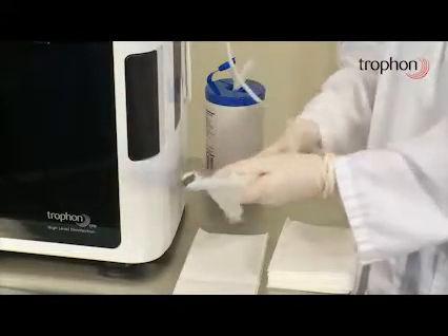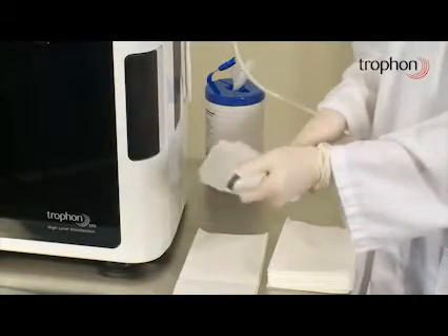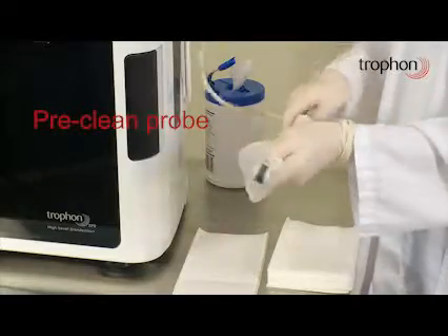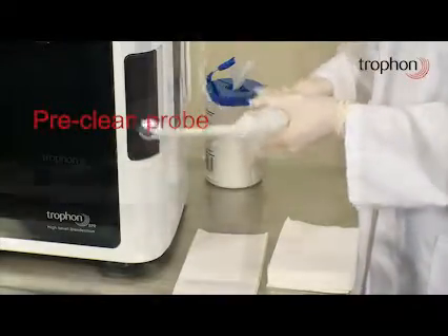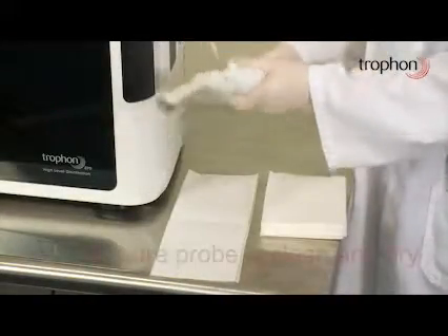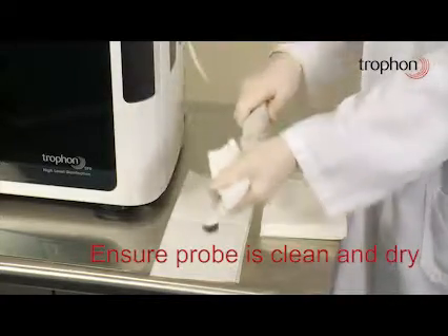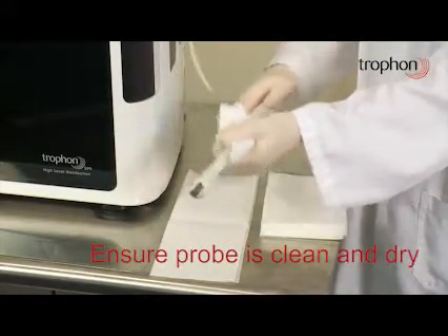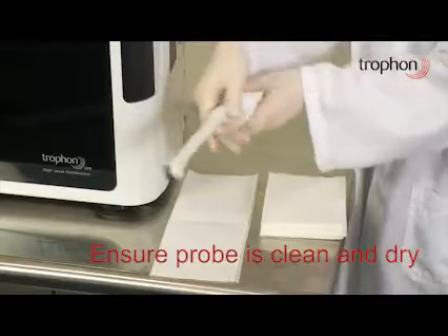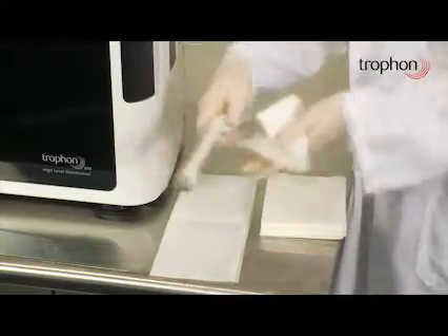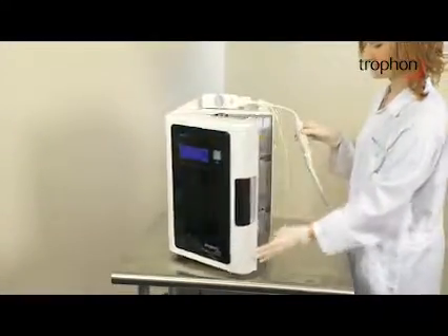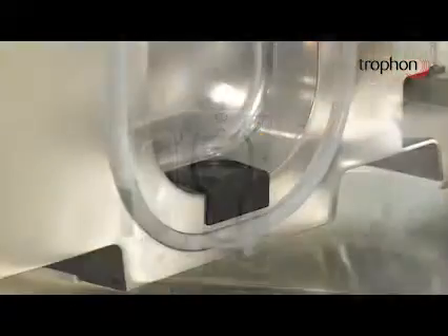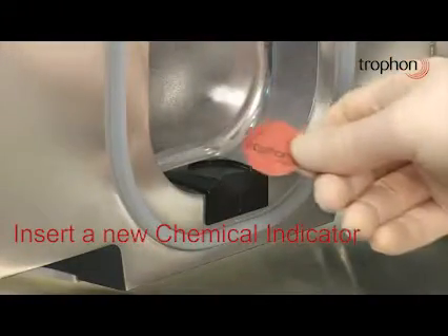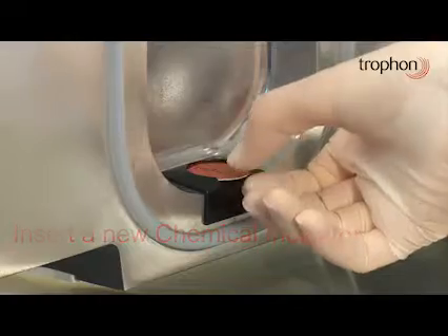Your Trophon EPR is now ready for high-level disinfection. Pre-clean the probe as per the manufacturer's guidelines. It is essential the probe is clean and dry. If the probe is not clean and dry, high-level disinfection cannot be guaranteed. Open the chamber door. Insert a new chemical indicator disc into the chamber door.